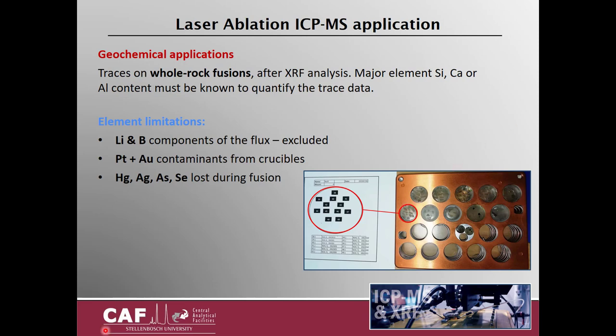There are some limitations to the elements that can be measured. Lithium and boron are components of the flux so they have to be excluded. Platinum and gold are often contaminants from the crucibles when fusing the samples. Volatile elements such as mercury, silver, arsenic, and selenium are usually lost during fusion.